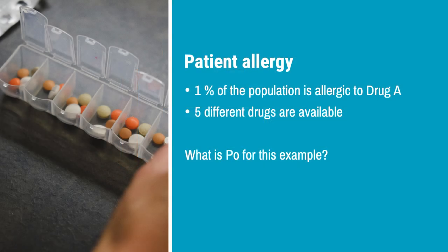I assume you have some basic understanding of risk management. If you don't, I recommend you watch the videos about risk management at Medical Device HQ. One of the most misunderstood statements in this field is that the probability of occurrence of harm should be set to 100% just because you're working with software. I can tell you that statement is wrong. The probability of occurrence of harm can be split up into two components: P1 and P2. P1 is the probability of occurrence of the hazardous situation. P2 is the likelihood that the hazardous situation will lead to harm. When people claim the probability shall be 100%, they refer to P1 — but even this assumption can be challenged. Let's look at an example where software is used to recommend the proper medication. We assume that 1% of the patients are allergic to drug A, and we have five different drugs to choose from.